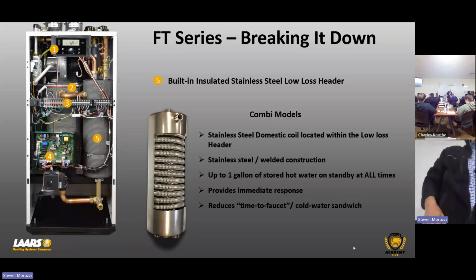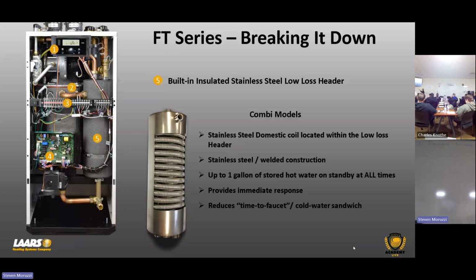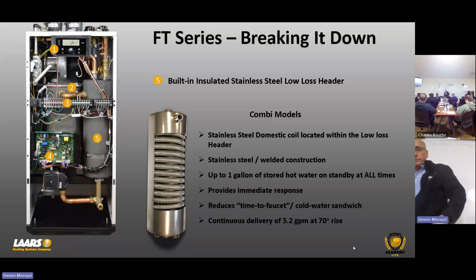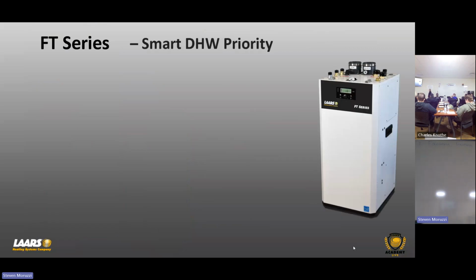Now also consider it's a 0-degree day and I have baseboard heat. What am I supplying for temperature on a 0-degree day for baseboard heat? 180. So what's happening to my domestic coil? If I've been running 180 for 20 minutes and I haven't had a demand for domestic, now someone gets up and turns on a shower, potentially I could be sending 180 degrees out, okay? That's why we want to make sure you have a thermostatic mixing valve installed out in the system. Does that make sense? And we'll get more into that in a few minutes. So again, that reduces cold water sandwiching, with continuous delivery of 5.2 GPM at a 70-degree rise.